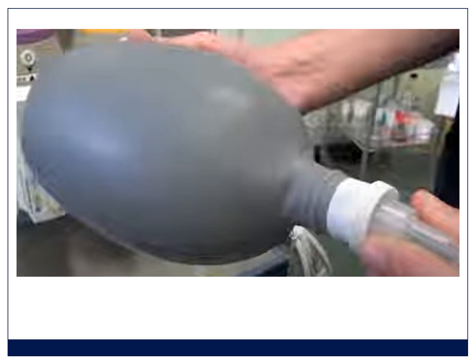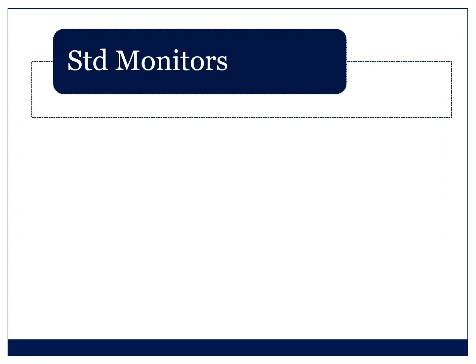And you can test whether you want to do pressure control or volume control. You can test that the ventilator is working. This is good for two reasons. It's testing the machine's working, tests you know how to use the ventilator. We're almost finished. The next thing you want to check is that you've got your standard monitors. This is usually ECG, blood pressure, oxygen saturation as a minimum.